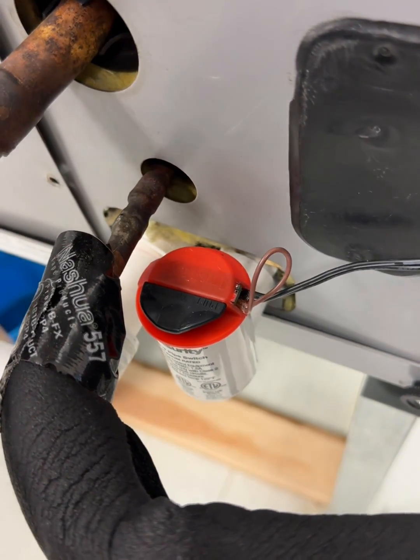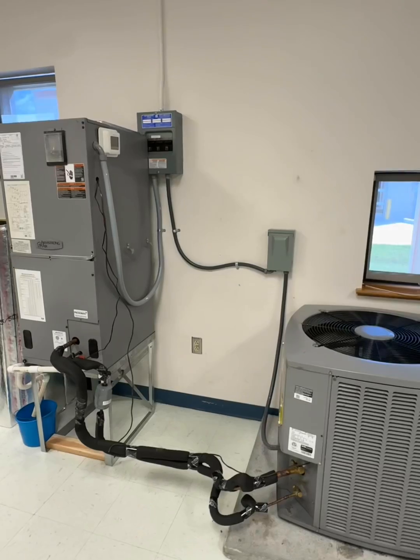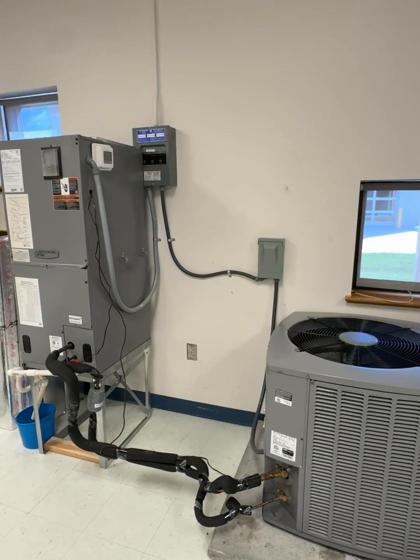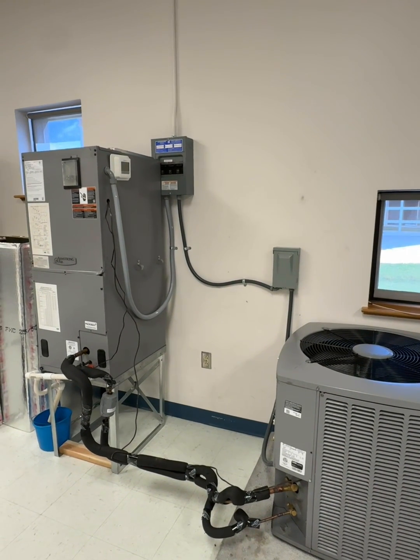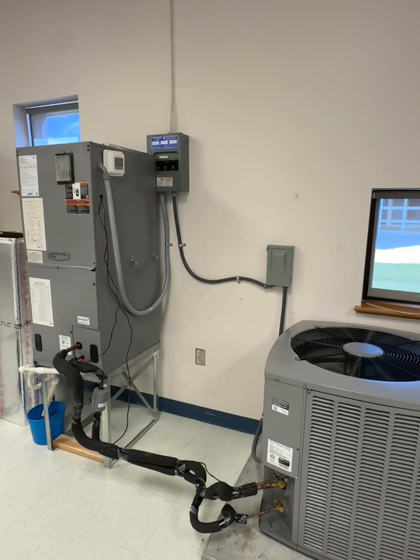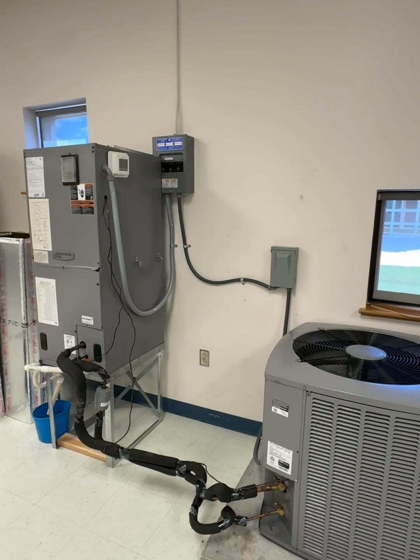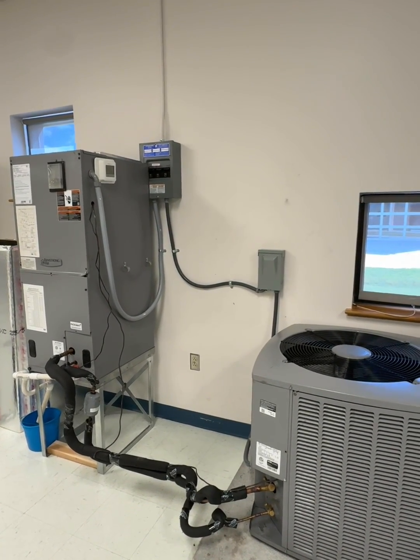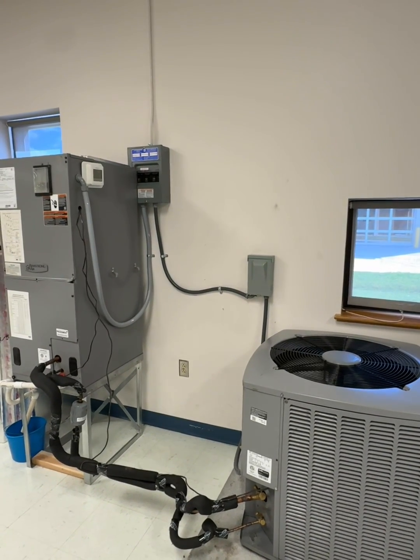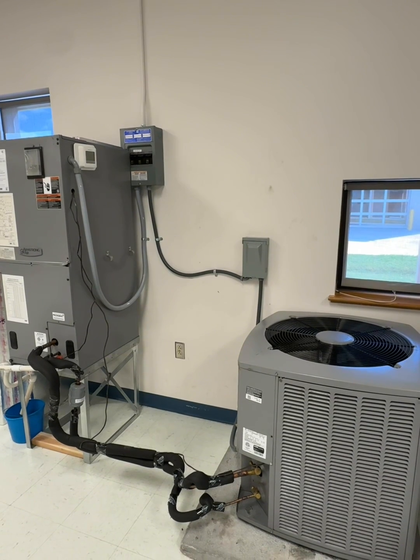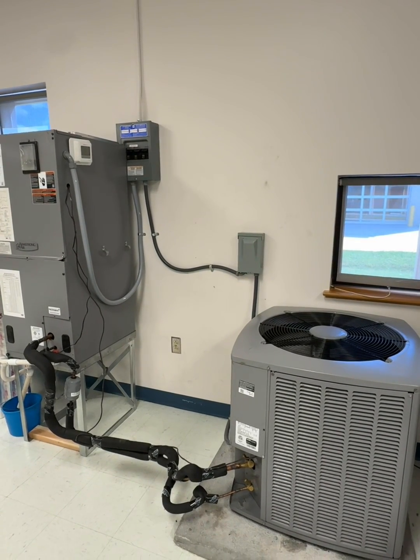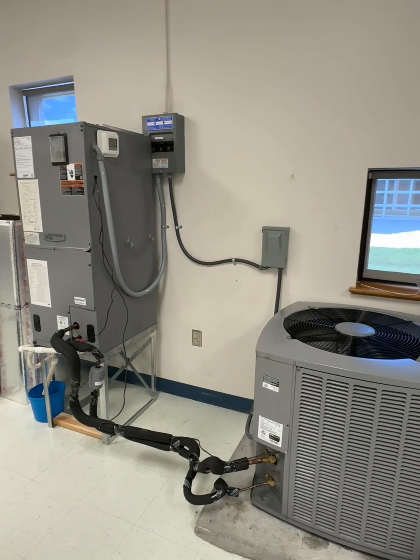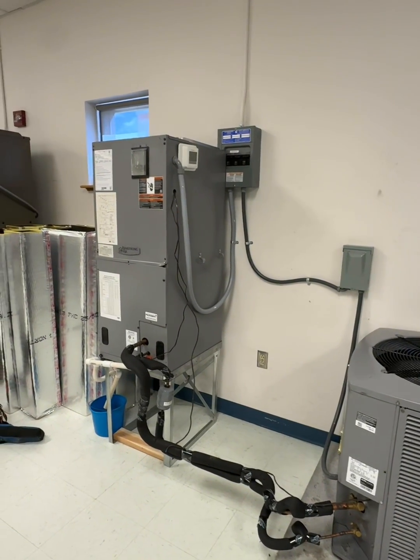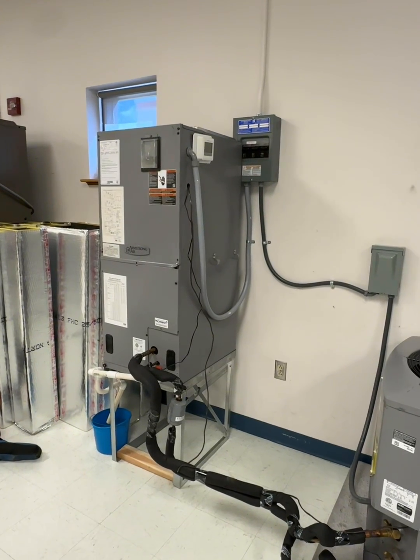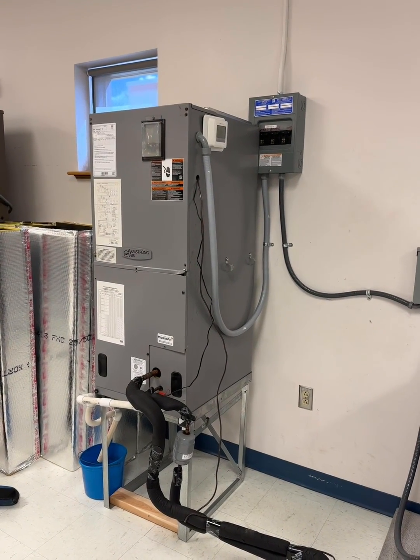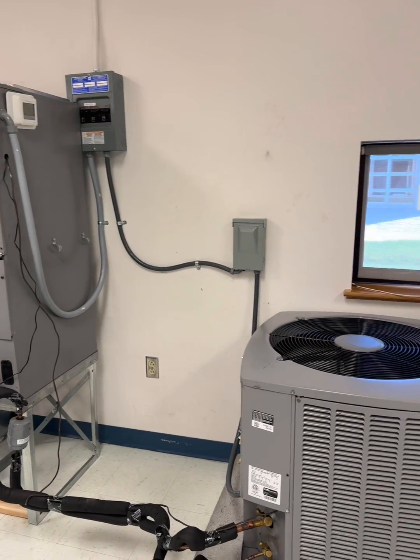So without the P-trap, and with the blower on, air will be sucked in through the pipes, allowing no drainage until the unit is off. It would eventually build up and cause leaks from overflow of water. While that unit is on, it would build up quite a bit of water. So it is necessary to have a P-trap, and the PVC in our system is crucial to it, because it allows efficiency in our units.